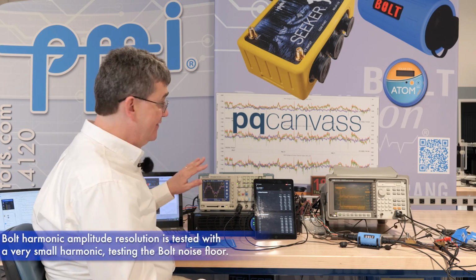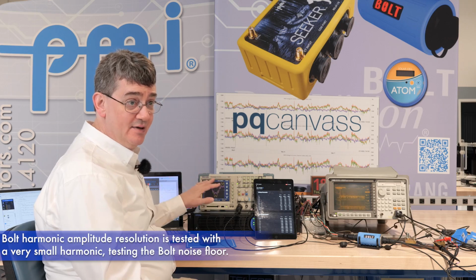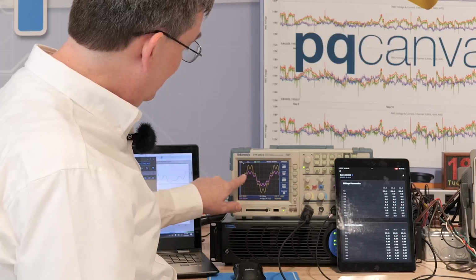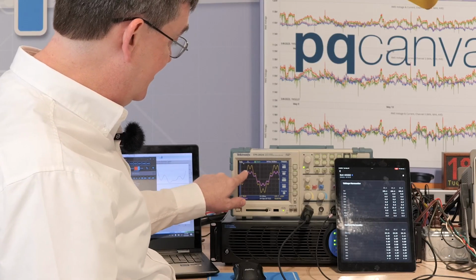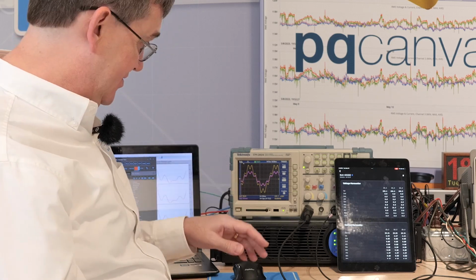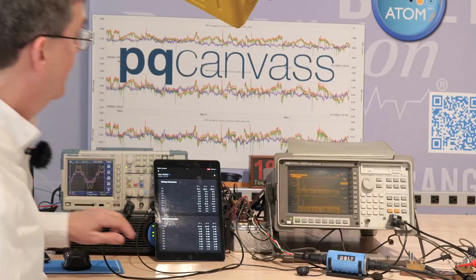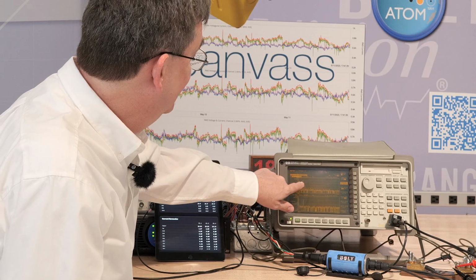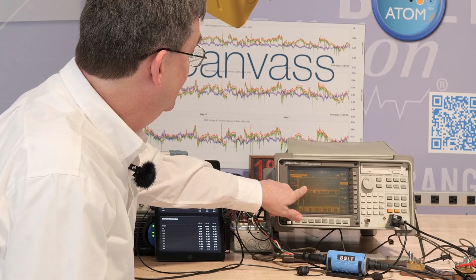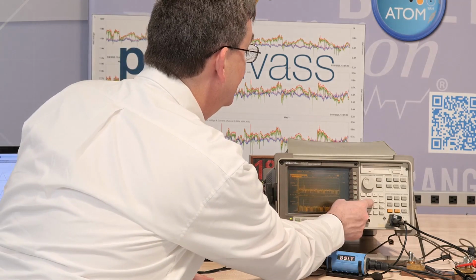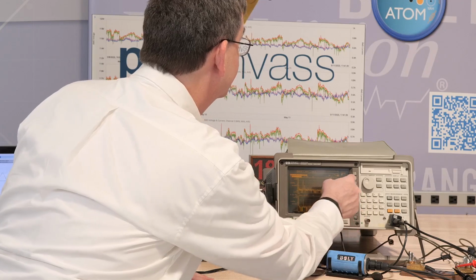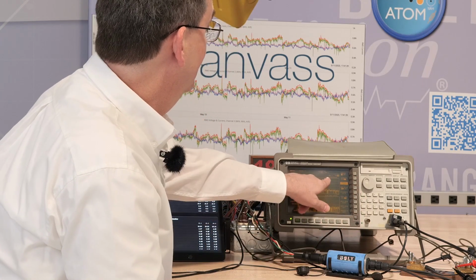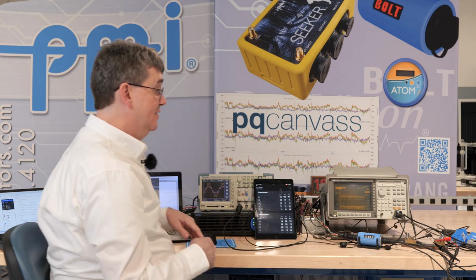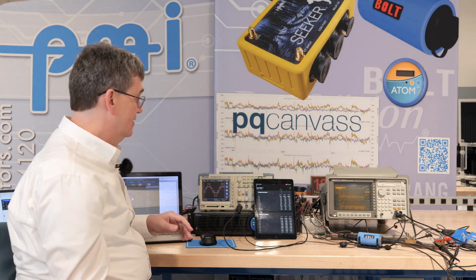With this pattern, we have a very large 7th harmonic and a very small 9th harmonic. We want to make sure the 9th harmonic is being measured correctly, even in the presence of a nearby large harmonic. So in the waveform on the scope, we can see it's mostly 60 Hz and the 7th harmonic. The 9th harmonic is going to be impossible to see in the time domain. So we can see 60 Hz, we can see the 7th harmonic is large, the 9th harmonic is very small here. Let's take a measurement, 540 Hz. We have roughly 10 millivolts times 20, that corresponds to 0.2 volts.